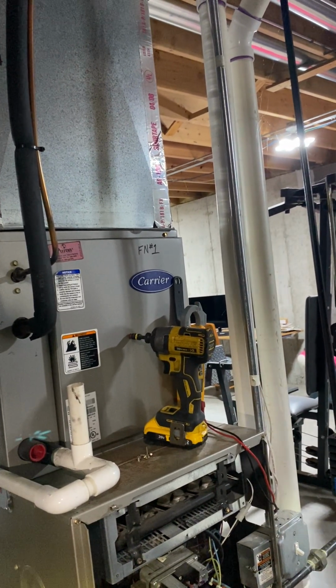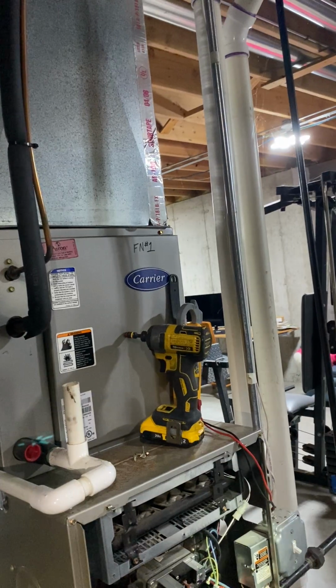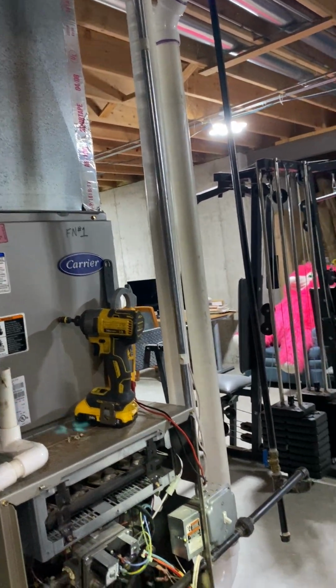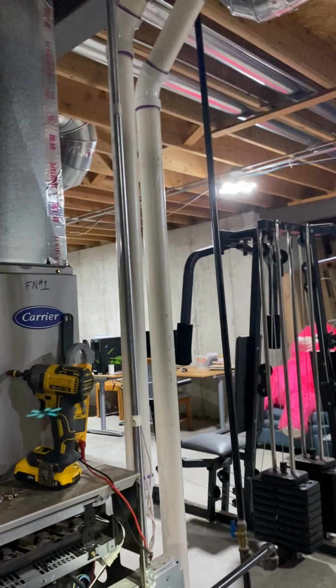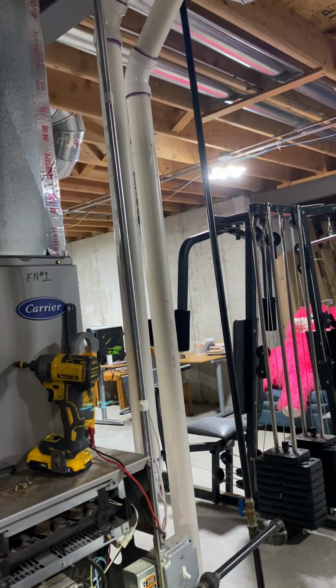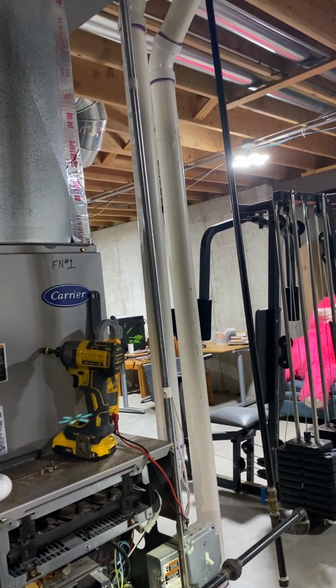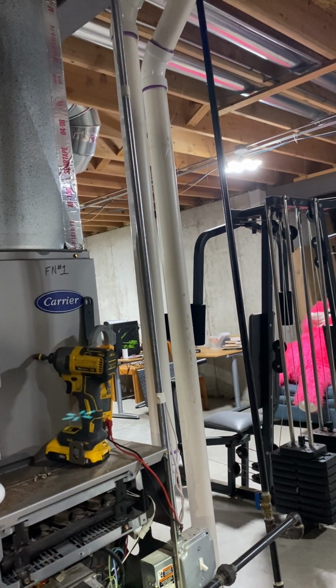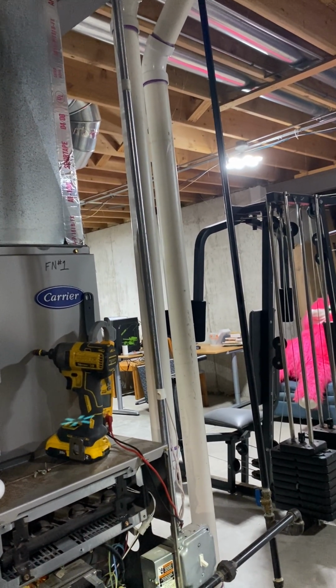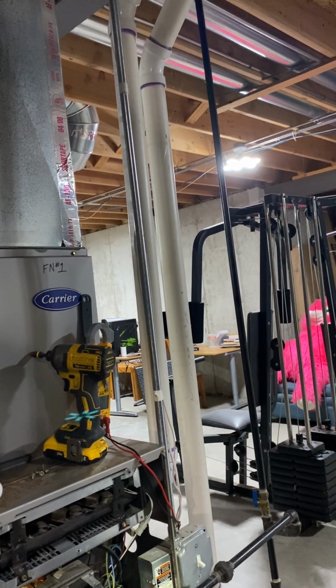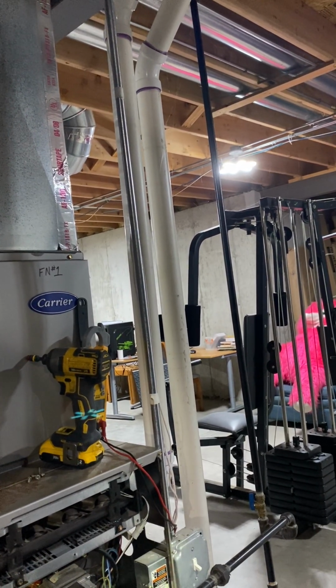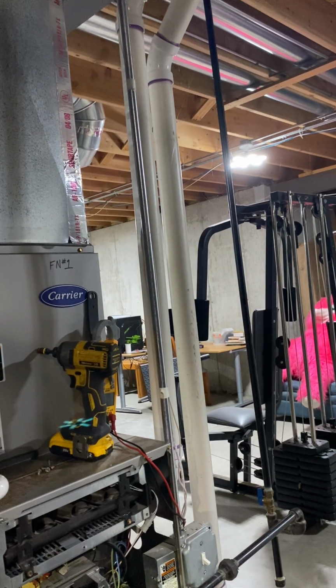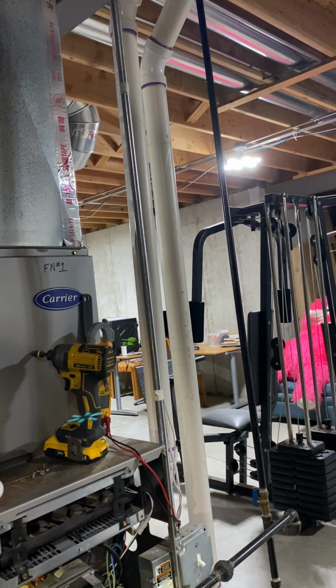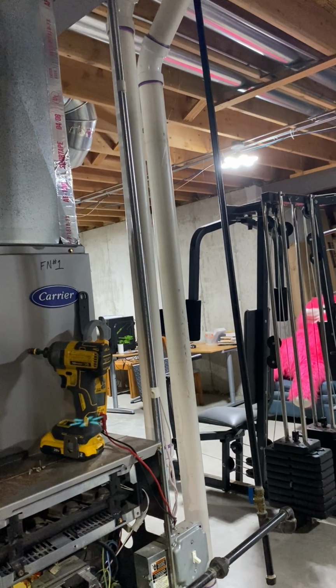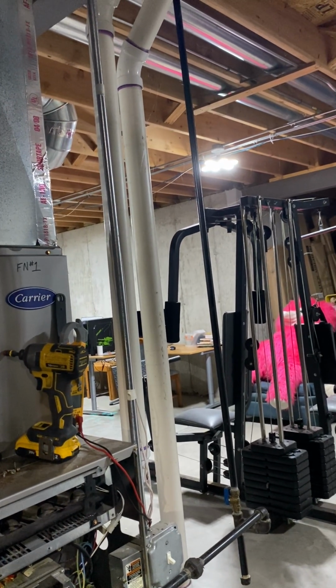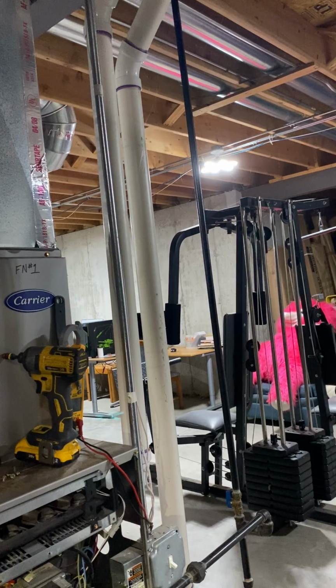Hello, this is Chris with Pure Climate. How are you? I'm doing well. So what's going on is that there is water present inside the system, and it's clogged up, and it's tripping your safety switches. So the heat is not coming on. What I want to do is clean out the water, clean out the P-trap of the clog that's in there, get everything cleared out, get it up and running, and then perform further testing. So far it'll be for 1 hour, no parts. You'll be looking at $449.